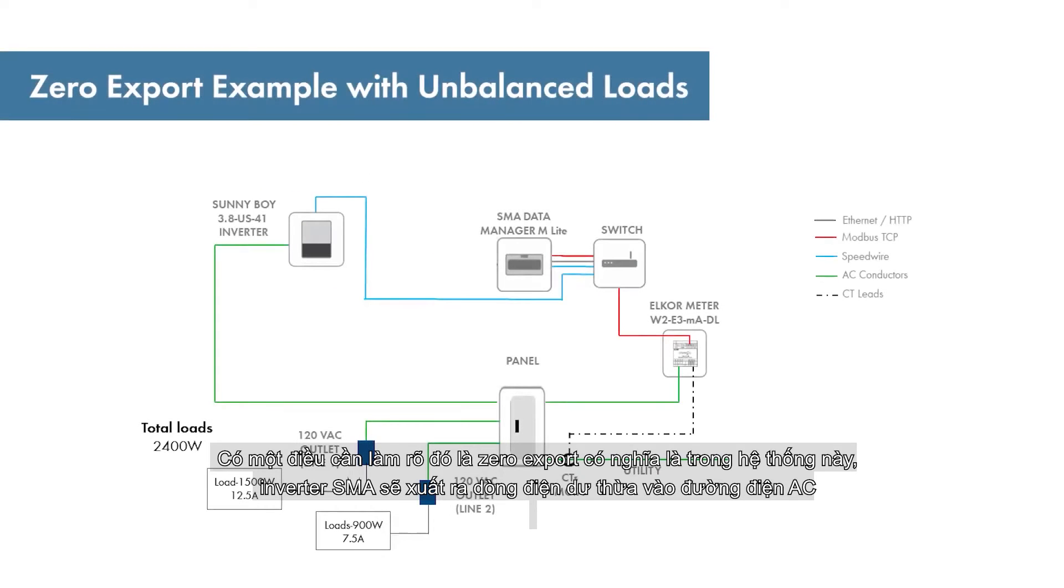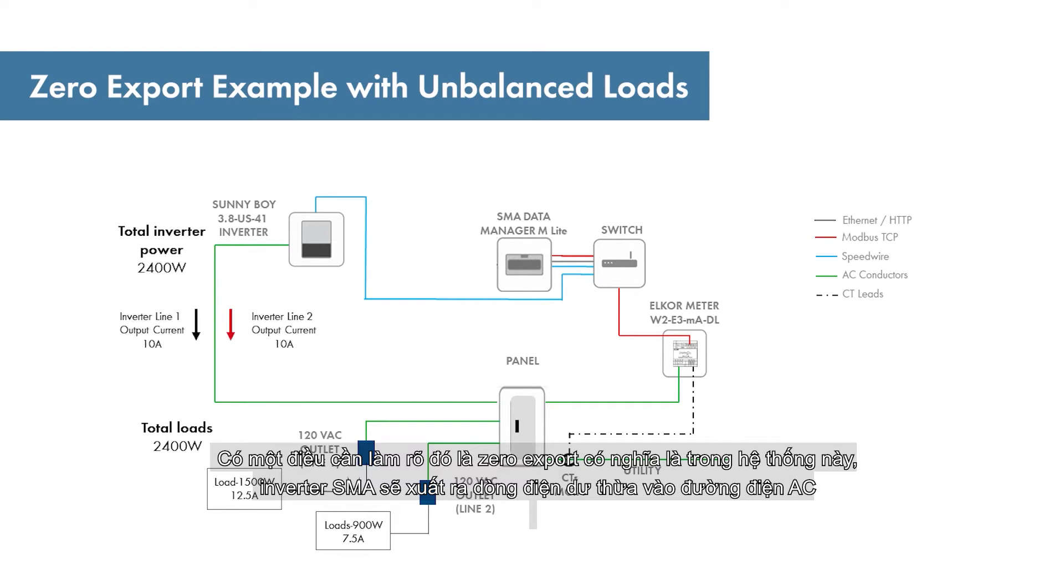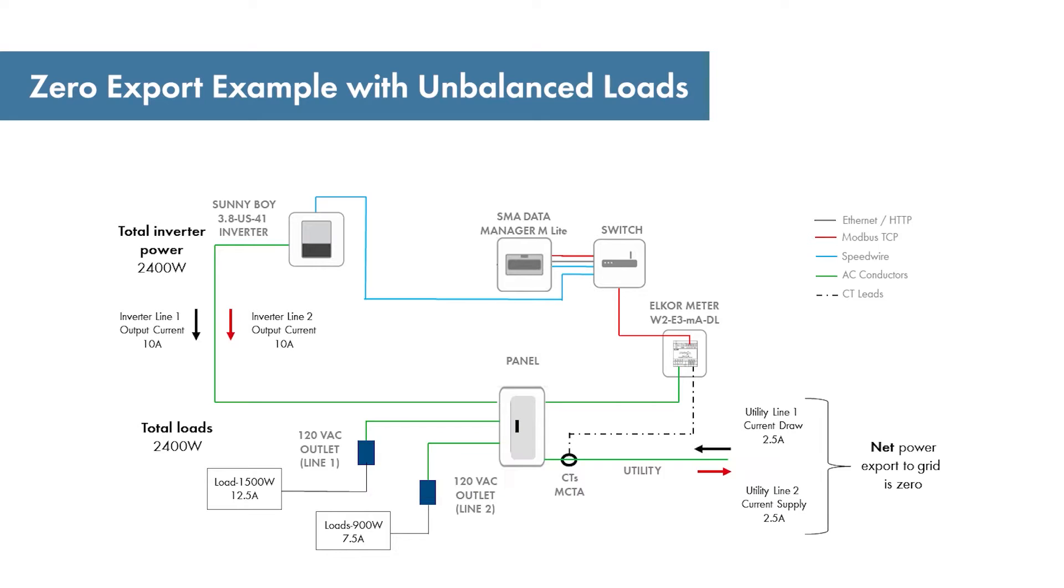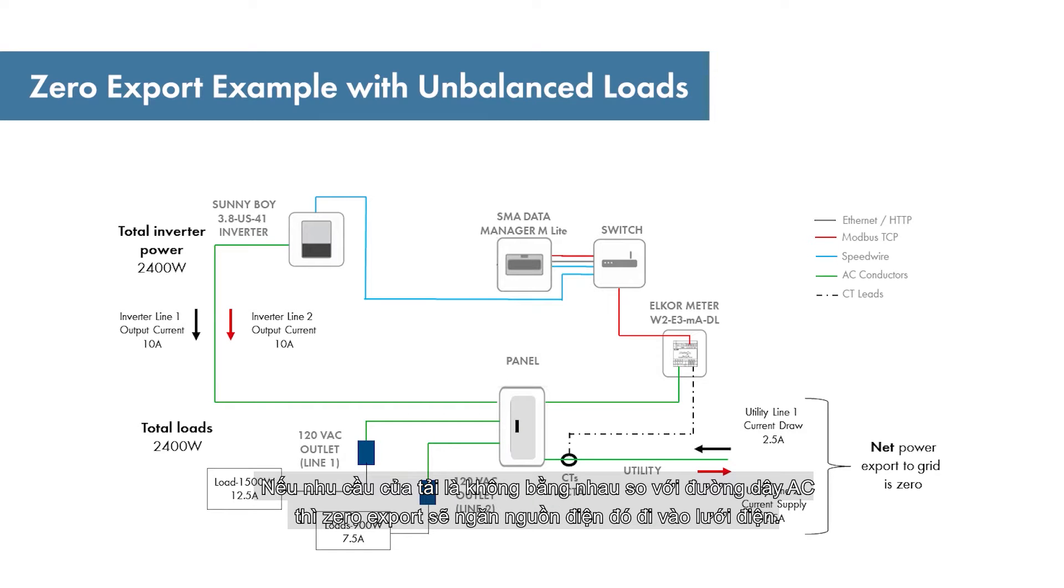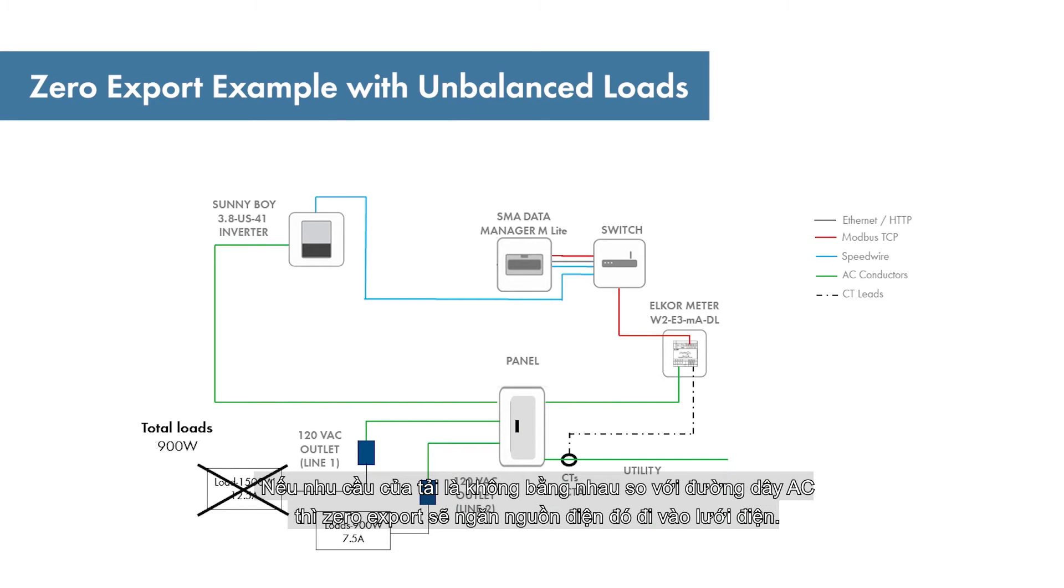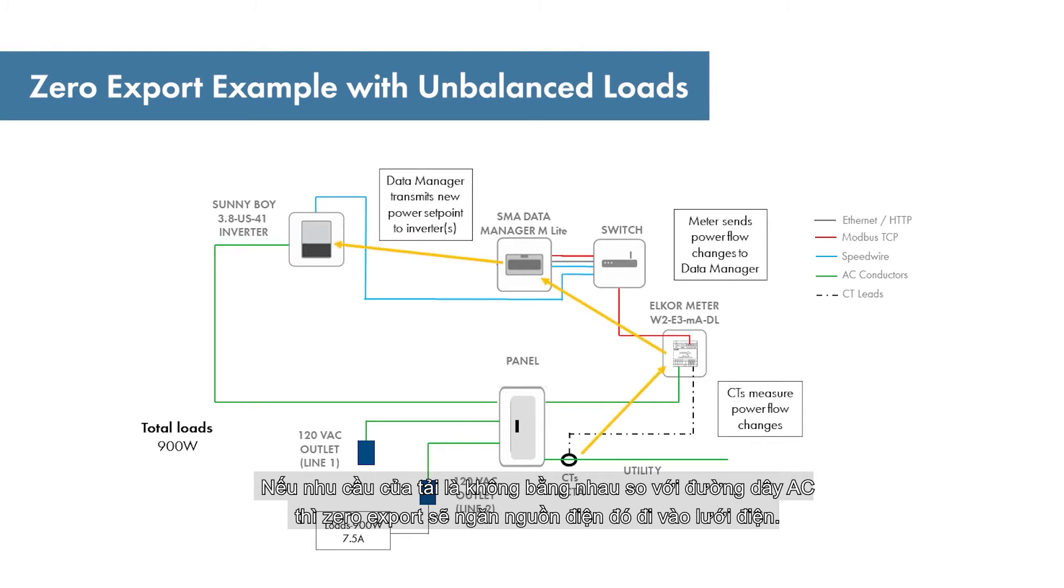One technical point to clarify is exactly what zero export means for this system. An SMA inverter will output balanced current on its output AC line conductors. If the load demand is not balanced across those lines, zero export will yield net zero power flowing to the grid.